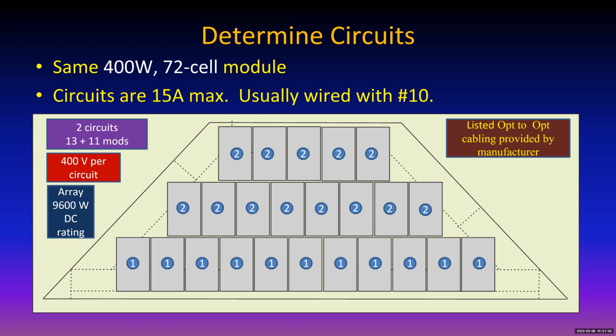Optimizer to optimizer cabling is provided by the optimizer manufacturer, so it's all UL listed. And it's open wiring, by the way, no conduits or anything, just open wires and proper cable management configurations. There's a junction box on the roof where you take these open wires and you run them into the junction box and come out through conduit to the inverter.